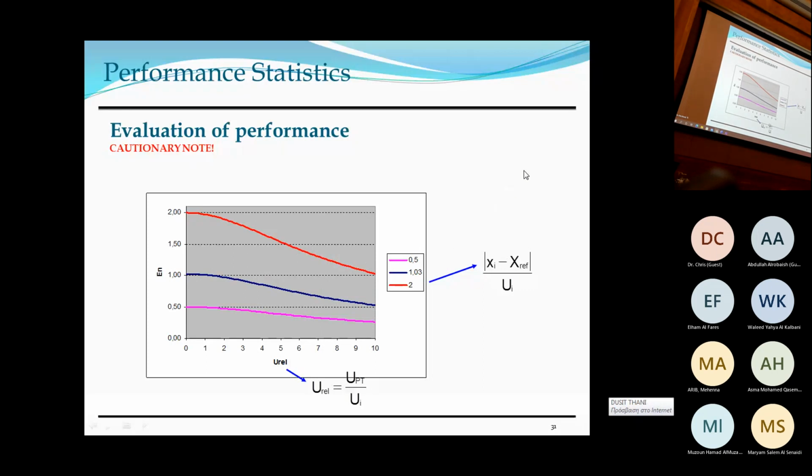So yes, the instability uncertainty has to be taken into account. However, it can influence the results of the conformity assessment that's being done through this test. So someone has to be very, very careful. This is why it's always a good idea to have a fit-for-purpose, stable, and well-defined measurand as a transfer standard.